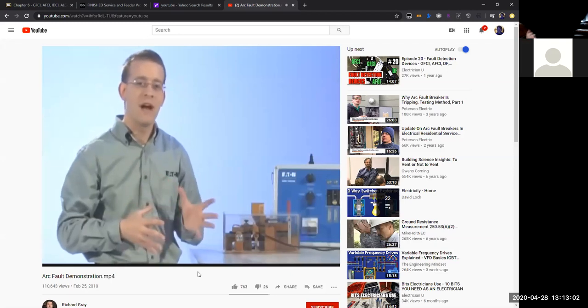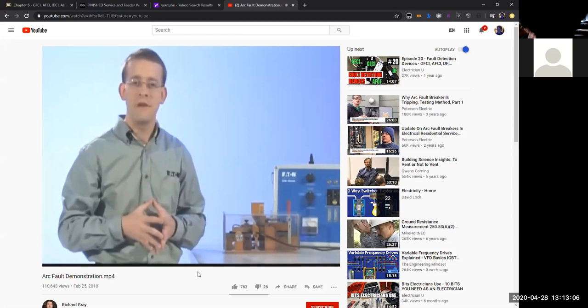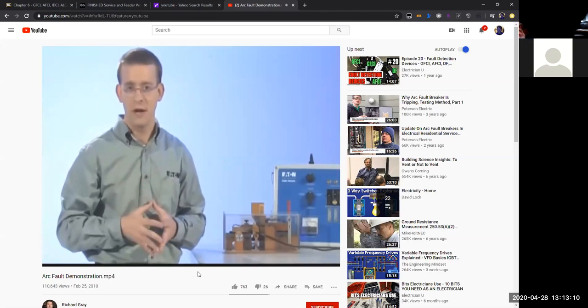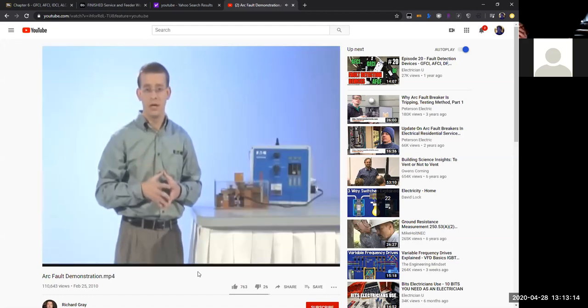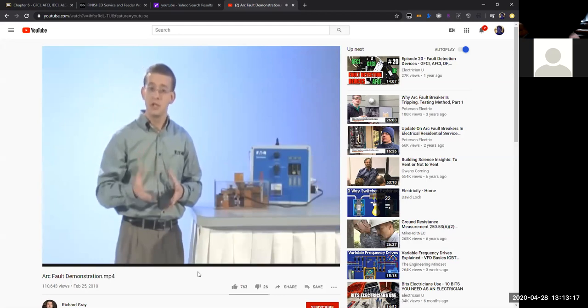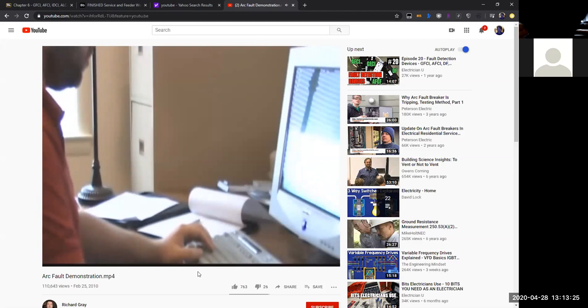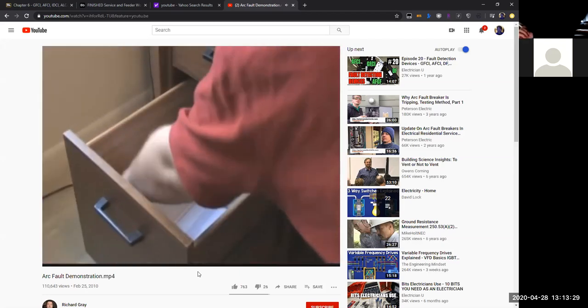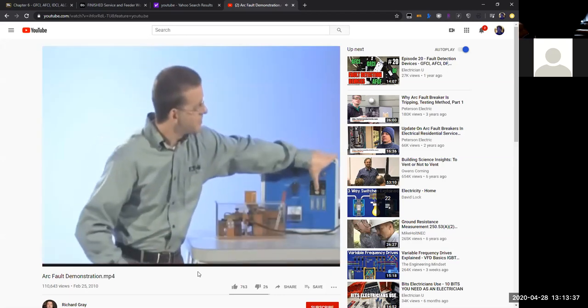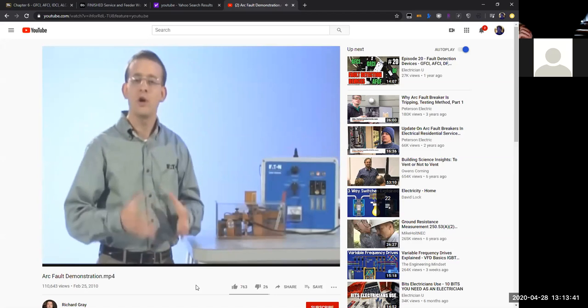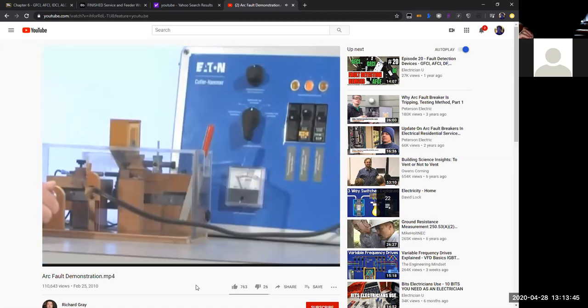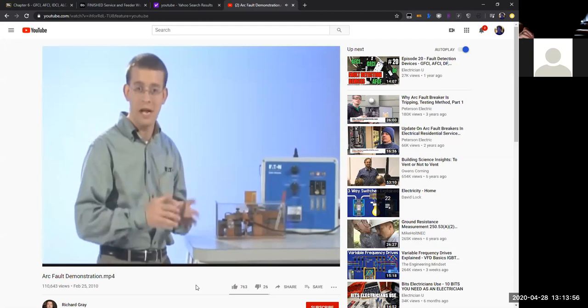While this AFCI breaker has been providing fire protection for many years, additional studies have found that another type of arcing also contributes to electrical fires. This arcing condition is called low current arcing and is most common in household cords such as extension cords, appliances, lamps, etc. In this situation, the phase or hot wire is broken, but the two severed ends are still close enough for arcing to occur between them, resulting in the arc actually jumping across the gap. Since this arc is in series with the load, the current will be limited by the load being drawn. This low current arcing is in the 5 to 10 amp range and won't be detected by the branch feeder AFCI.